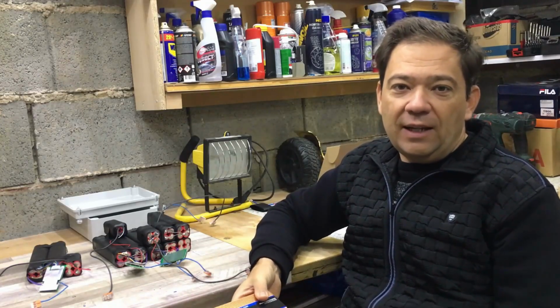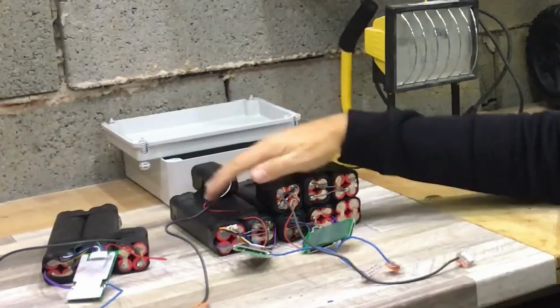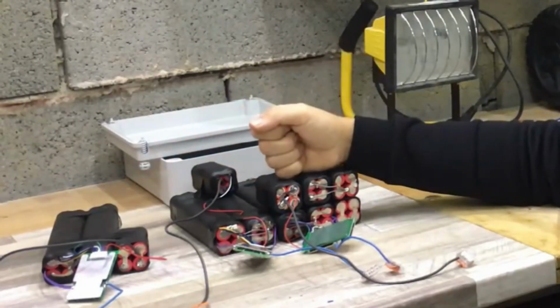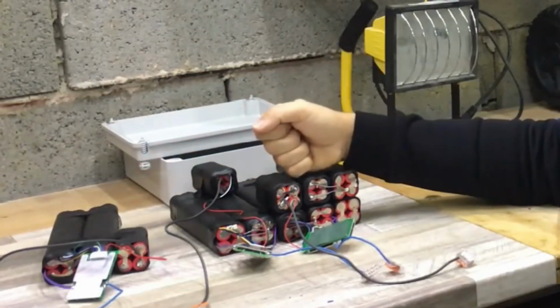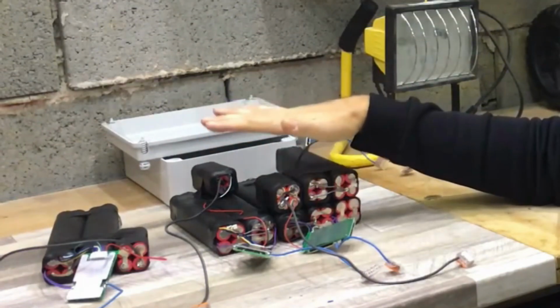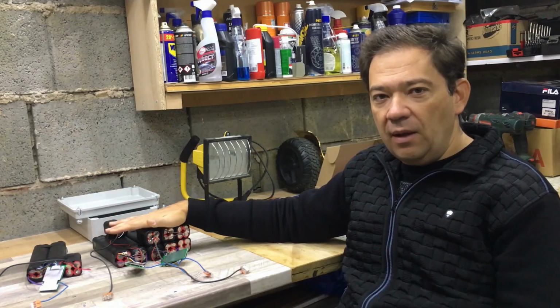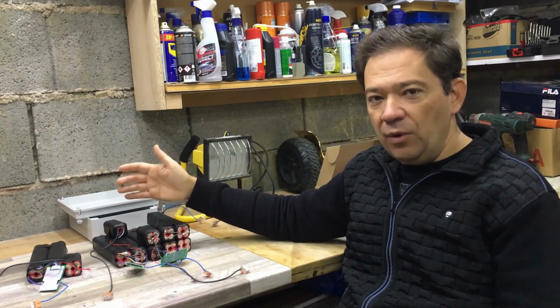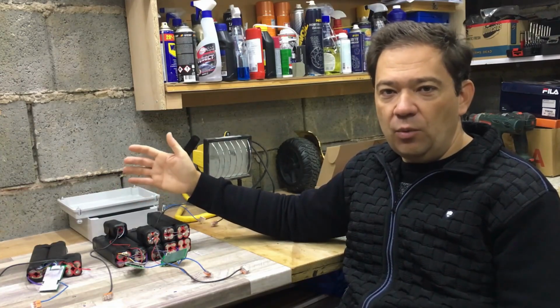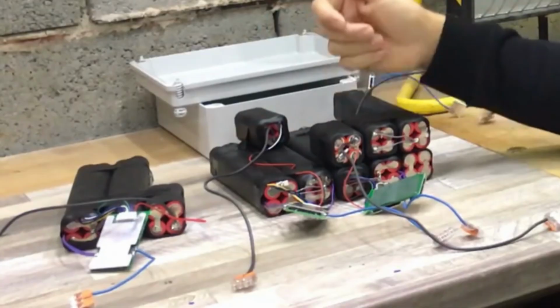So it's a 10 kilowatt inverter, but in practice it'll be able to deliver 2 kilowatts. In this pile here under my hand, there are a total of 112 lithium cells, each one 2.2 amp hours. I planned for the whole thing to be able to deliver 80 amp hours. So 80 times 28 volts is roughly 2.2 kilowatts, which is about what this system is capable of.